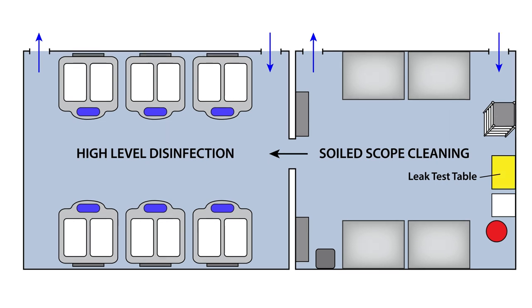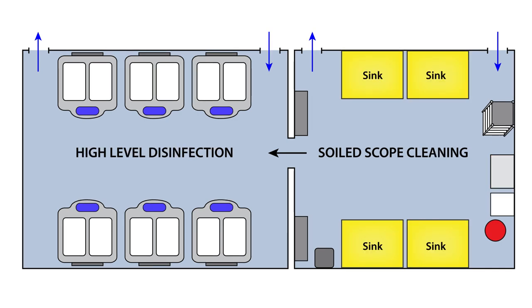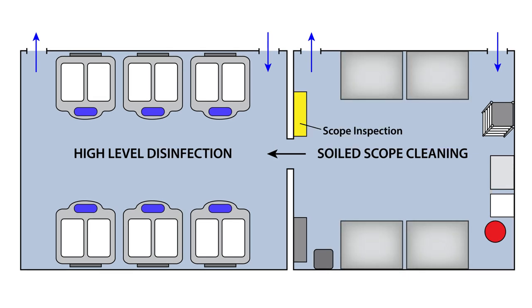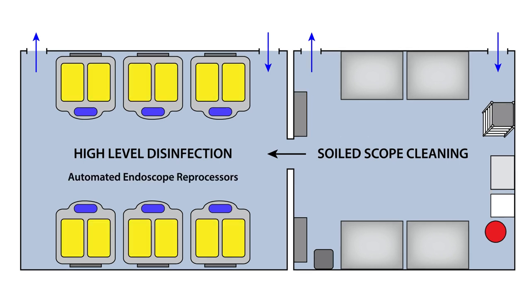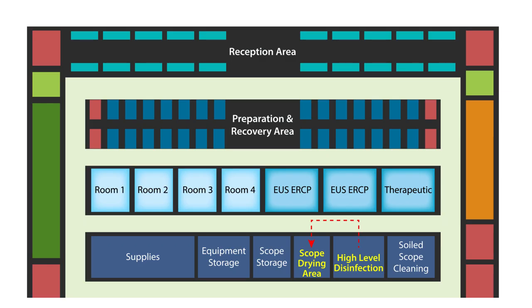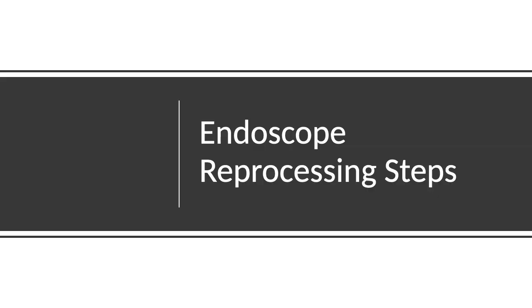So once the scope comes here, it gets tested for any leakage. And following the leak test, it goes to the sink for cleaning, brushing, and so on. And then you check the scope for any damage or whether the cleaning was perfect or not. If not, you go back to the same cycle. Once you're happy that the scope was clean, then you take it through the next level, that is high-level disinfection, for getting rid of the microbes. And following that, you take it to the scope drying area for drying before it gets stored. So there are lots of steps that the scope takes in its journey. And let's find out what each step involves.